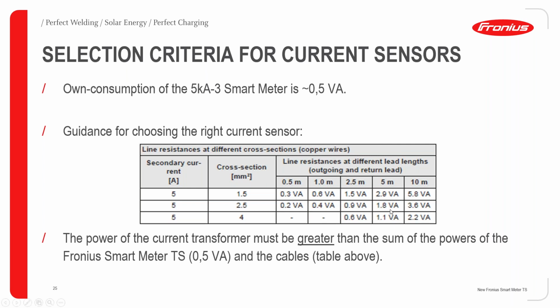So there is a small table mentioned here which shows the line resistance at different cross sections for a copper wire. For different cable lengths and different cross sections, the power will be different. For example, if you look into row 3 in the table, you can see the cross section for 1.5 copper cable is, if you are using 0.5 meter cable, then the power of this cable is 0.3 VA. So the total power of the smart meter and the cable is here 0.8 VA. So this is how you calculate.